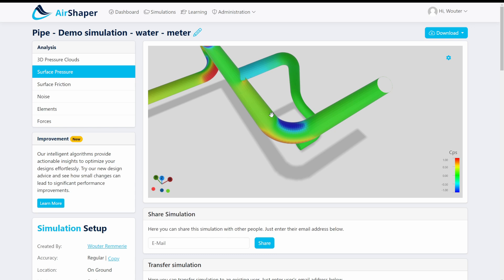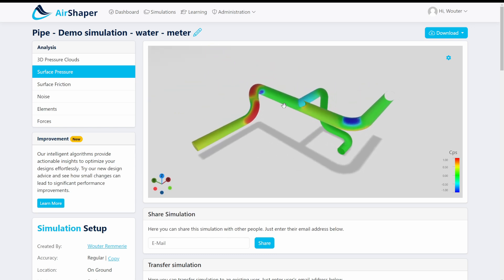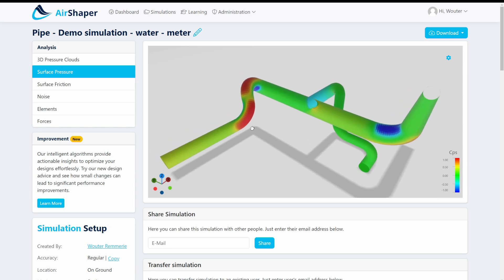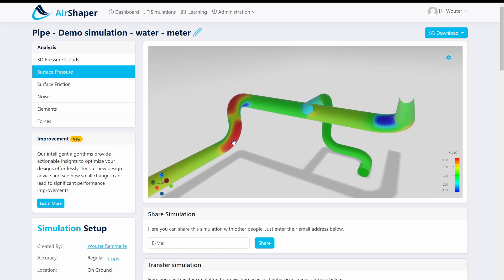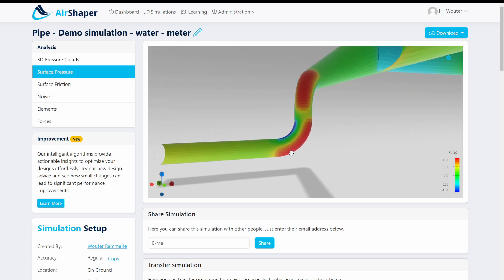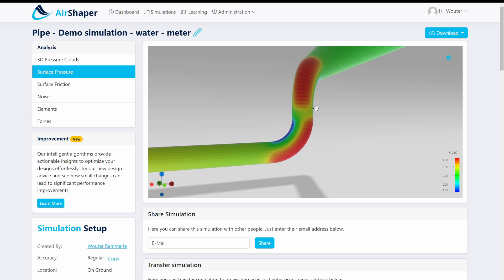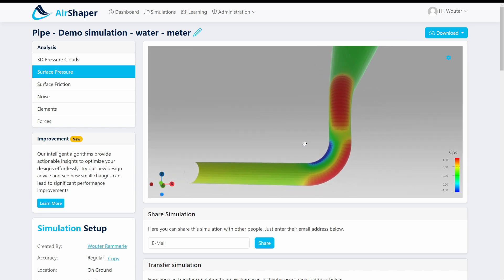If you look at the pressure, so what is happening with a flow like this, you have a high pressure at the beginning so that's why it's slightly yellowish compared to the greenish darker greenish here at the outlet and it's scaled automatically with respect to the maximum pressures that you have in the system. And the flow velocity so this is what we saw before so the flow actually hits the outer corner of this pipe section this bend and the inner corner features a low pressure as the air accelerates around the corner but actually wants to get away from this surface.